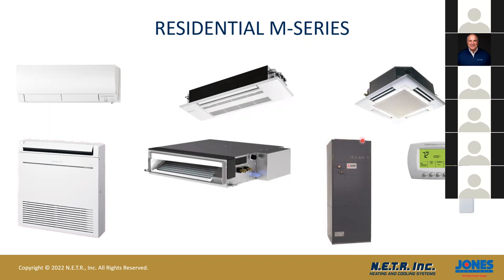And sometimes we use these to replace furnaces. We replace existing air conditioning systems. If we have a person that has air conditioning and wants to put an air source heat pump into their home for heating, might already have heating in the home, might be using this as supplemental heat, but this replaces standard air handlers in homes and comes up to 36,000 BTUs in the M series.